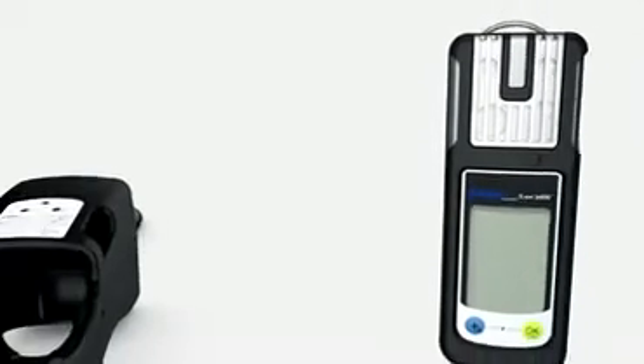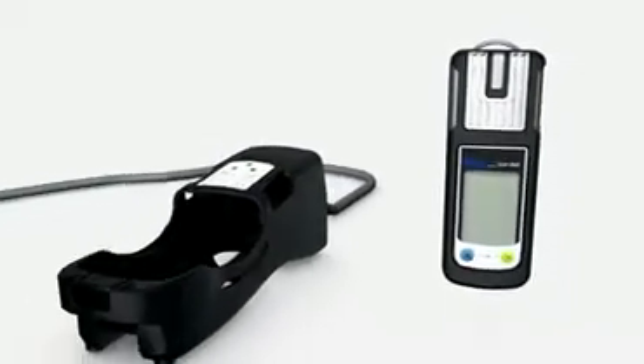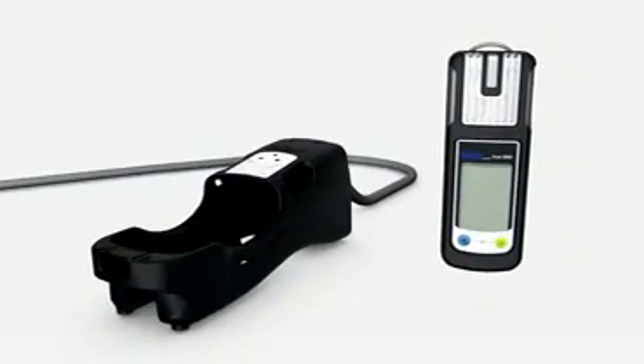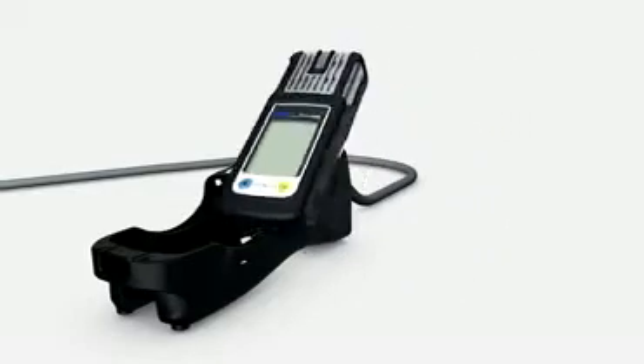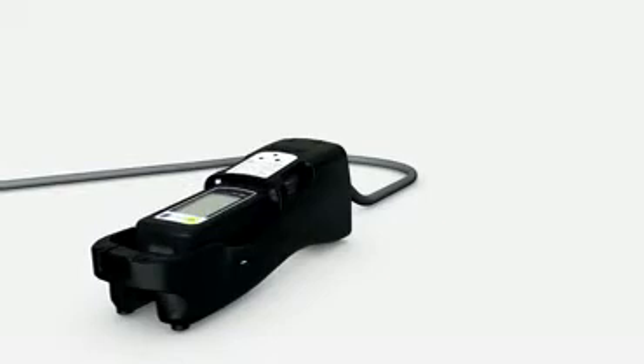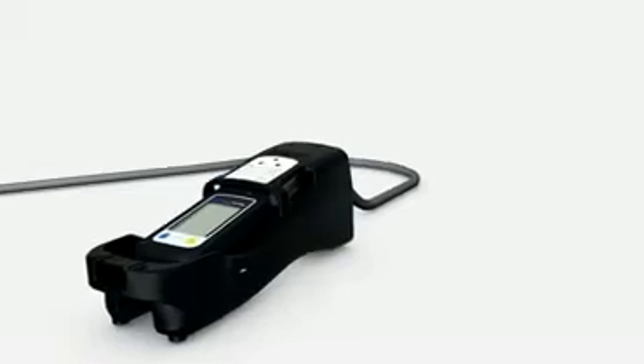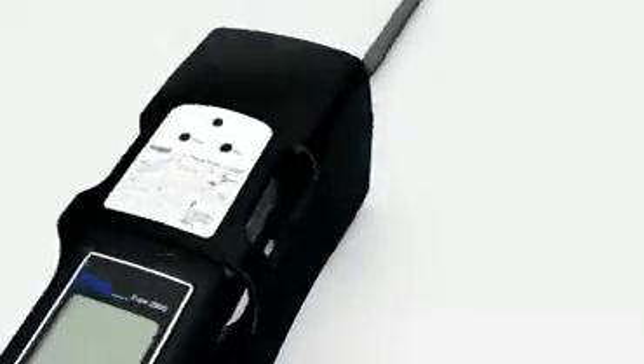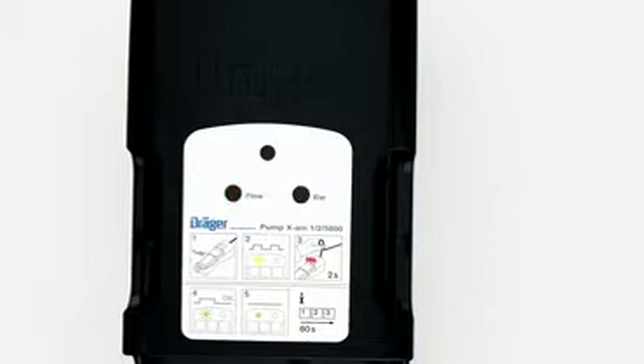The X-am 2500 can also be used with an external pump for atmosphere tests in confined spaces. Place the switched-on device inside the pump. Press down until it clicks into place. The LEDs briefly turn green and then red, accompanied by an audible signal. The pump now starts automatically and initializes the flow test. At the same time, the yellow LED flashes and an audible signal can be heard.